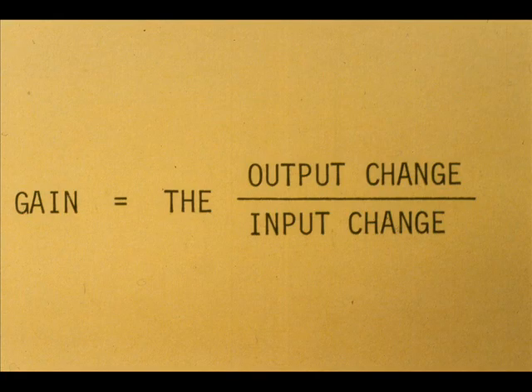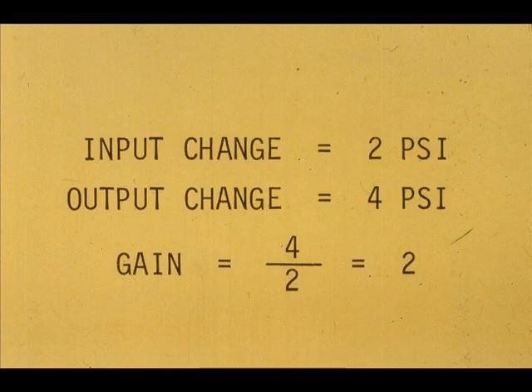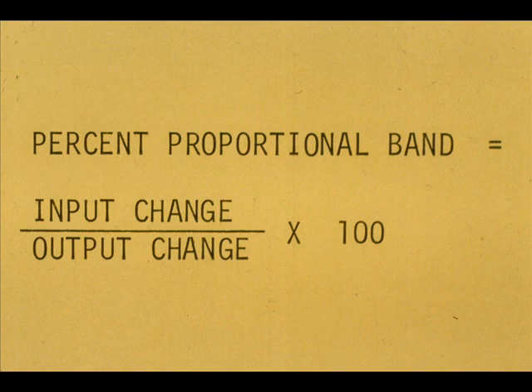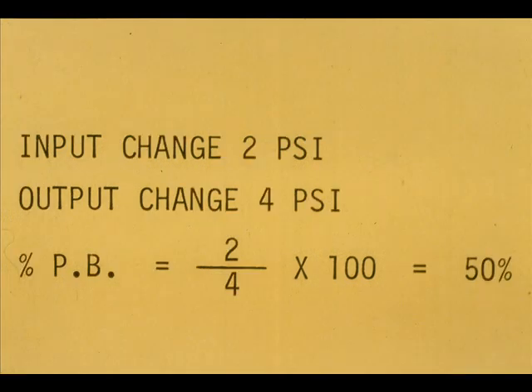Gain equals the output change divided by the input change. If a two-pound input change to a controller gives a four-pound output change, the gain is two. The units could just as well be milliamps. Percent proportional band equals the input change divided by the output change times 100. If a two-pound input change to a controller gives a four-pound output change, the proportional band is set at 50%.